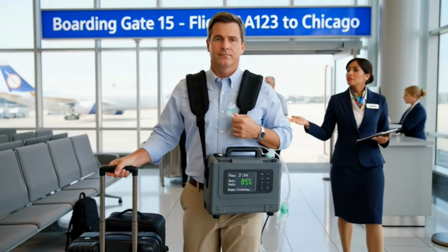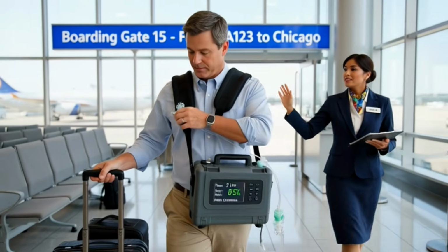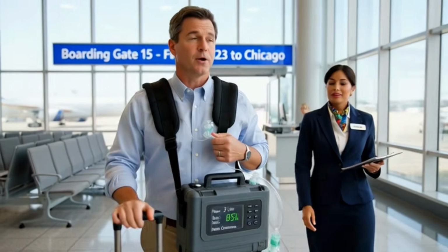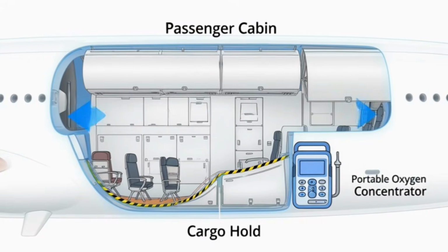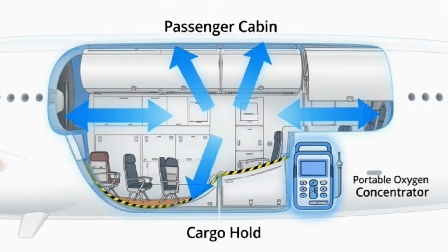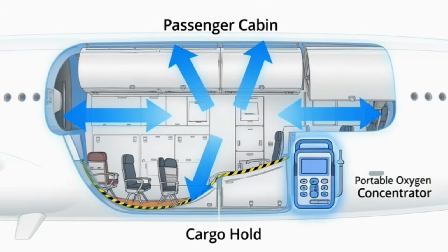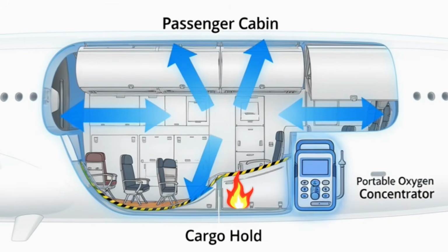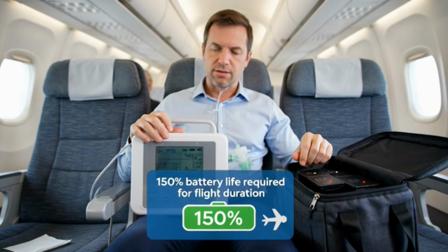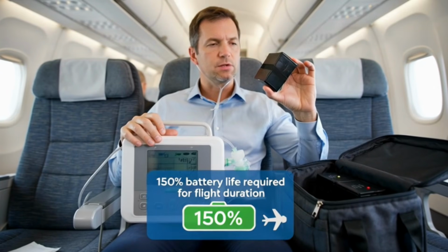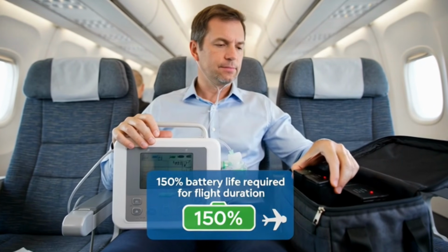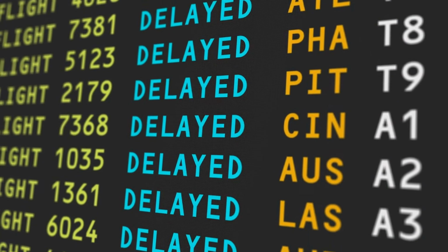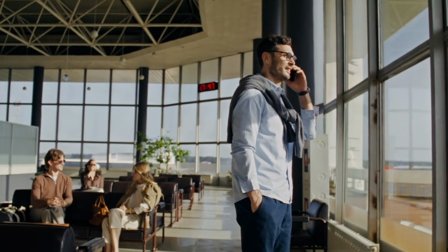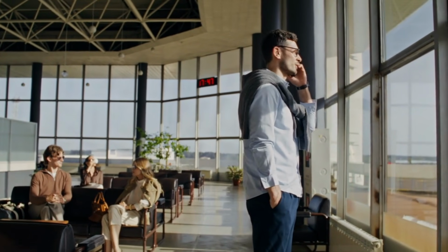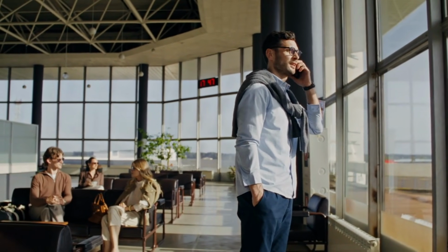Portable oxygen concentrators, POCs, must come on board with you. They cannot fly in the cargo hold. The FAA requires this because the pressure changes down there can affect the device and the batteries are a fire risk. Airlines require you to have enough battery life for 150% of the total flight duration, including potential delays. Call your airline at least 48 hours before your flight to confirm their specific requirements.